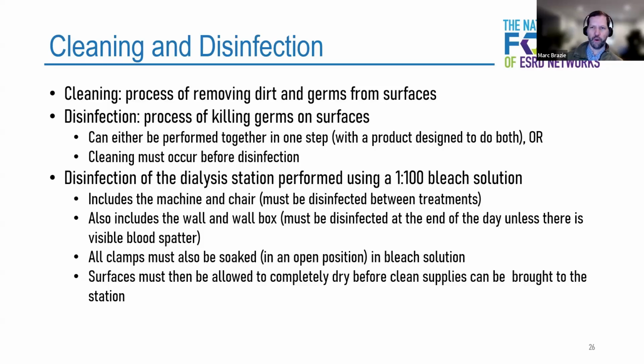And then the wall and the wall box behind the dialysis unit, where you might have your central acid bath, or if you're still using a central bicarbonate loop, where you might have your central bicarbonate loop coming in, that needs to be disinfected just once at the end of the day, unless there is any obvious blood spatter or there's a spill. Then it needs to be disinfected right away.